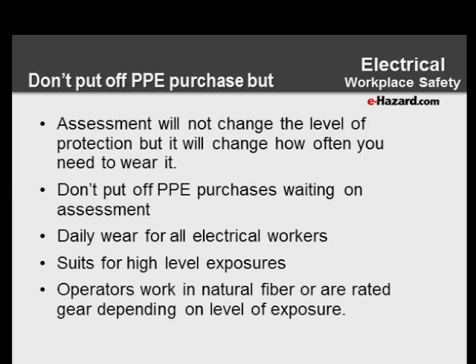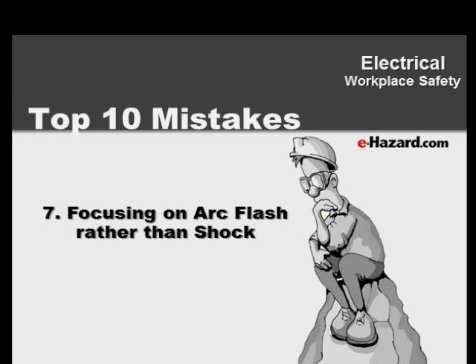I love this idea because we've seen it work so well for so many companies. Instead of making them wear long sleeve cotton shirts, put them in an arc rated welding sleeve and arc rated gloves when they operate disconnects, say 480 volt disconnects, something that can give them a burn. It's better to put them in a small amount of PPE than to go overboard or force everybody to wear a long sleeve shirt all day when they're only exposed maybe once or twice a day operating a disconnect or some electrical device. Make sure it matches the hazard, but don't overcompensate.